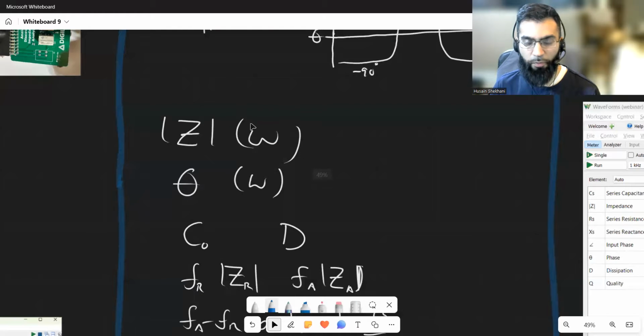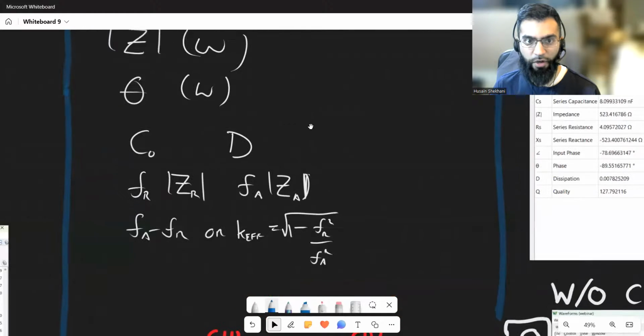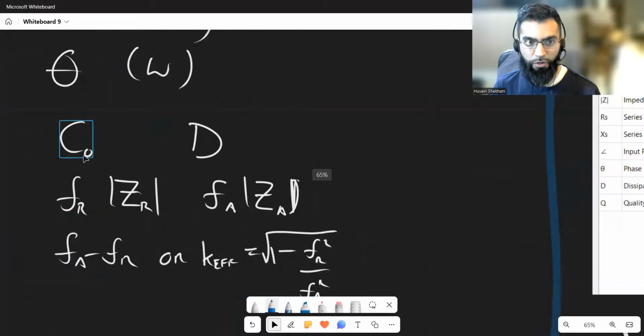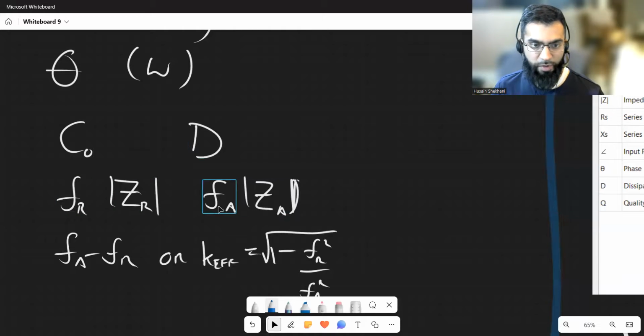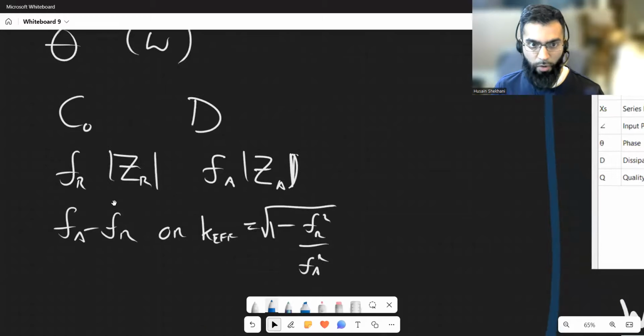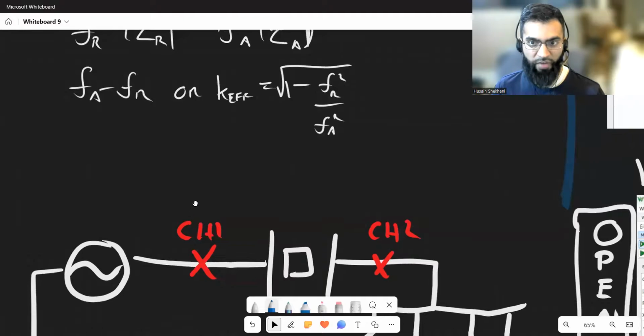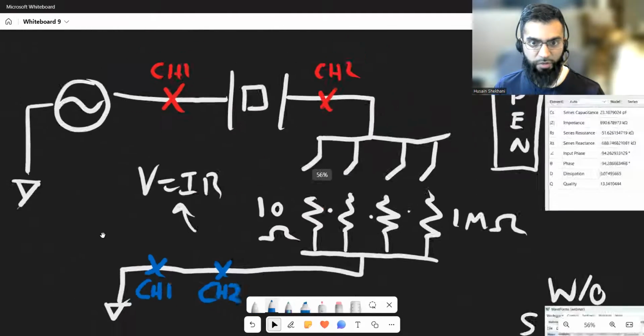The important parameters we look to measure in ultrasonic transducers are typically capacitance, the dielectric loss at an off-resonance frequency, the resonance frequency, the resonance impedance, the anti-resonance impedance, and the anti-resonance frequency. We may also look at admittance and series resistance - I've discussed that in other videos.